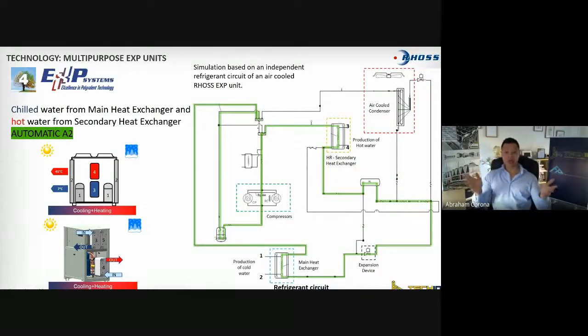In simple words, I like to say that sometimes it's like we have transformed a standard chiller into a water cooler, right? And this is because we're using all the heat that we were before wasting to the environment, we're using it in the system, all right? Instead of using the cooling tower. This is only to give you an idea of what happens internally. And keep in mind that this is the most efficient point of the Polyvalent heat pump, because basically you're using everything you were wasting.